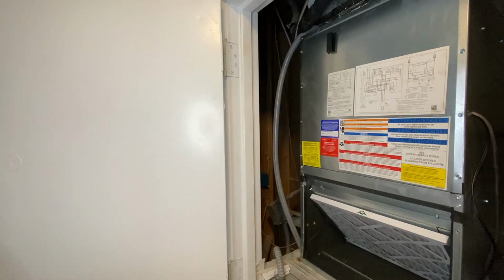The other way this is helpful is it really enhances home comfort by allowing the air conditioner to continuously spread air around the house at low speed, getting rid of hot or cold patches. The third reason it's highly recommended is that it enhances any indoor air quality equipment installed on your unit, such as high performance filters or UV sterilization systems in the supply air duct. Since the air is constantly moving through the system, you can take advantage of these indoor air quality systems that constantly need air moving through them.